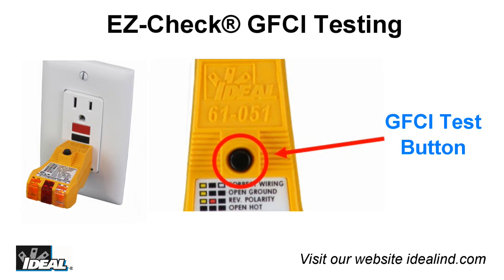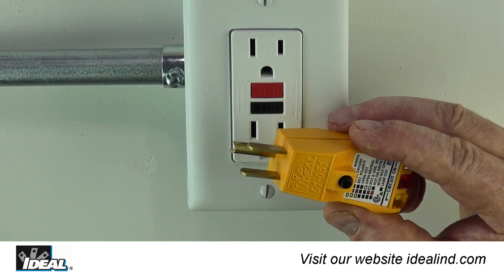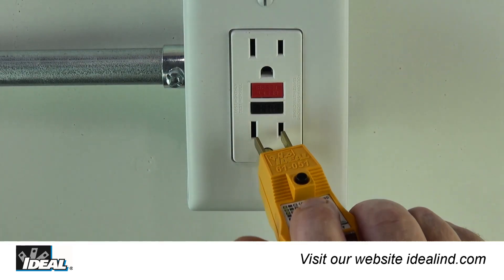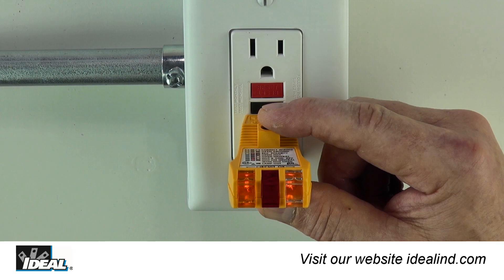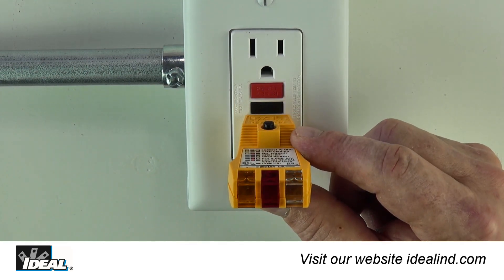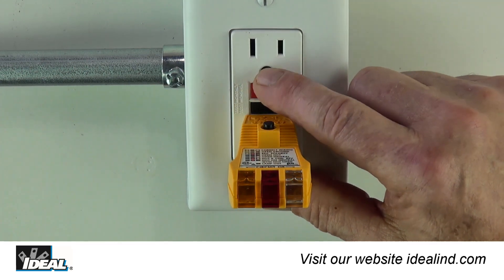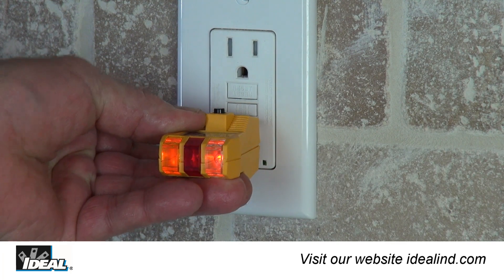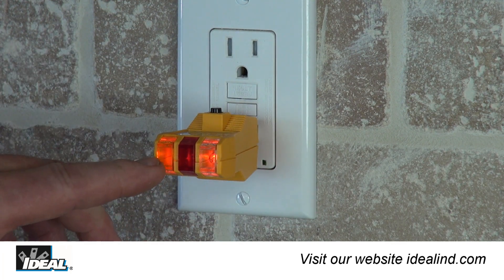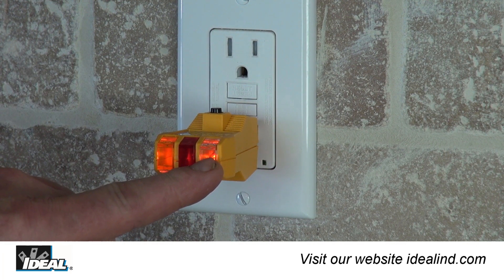The EZ-Check tester can also be used to trip a GFCI receptacle, ensuring that it is working properly. Simply plug the tester into the GFCI, or a receptacle in that circuit, and with both outside lamps lit, simply push the test button on the top of the tester until the GFCI actually trips, or for as long as 6 seconds. Typically, the GFCI under test will trip immediately and both lights on the tester will go out.